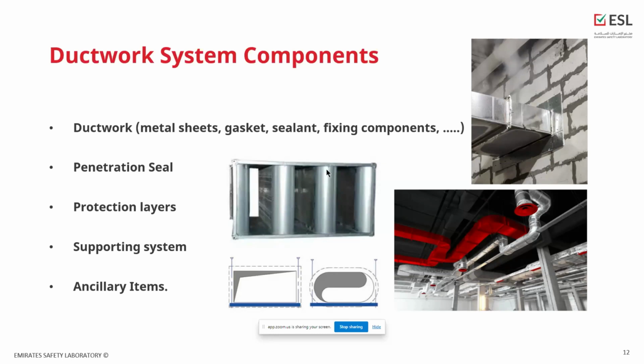This is the penetration of these elements, to not let the fire spread from one fire zone to another. So that's why the penetration seal is part of the system which will be assessed during the test. For the protection layer, we have coating or insulation just to protect the ductwork, and we also have the supporting system to support the installation, either horizontal or vertical. And we also have some ancillary items, like the sound attenuator and the VCD. All this, the sound attenuator, may be installed with the system.